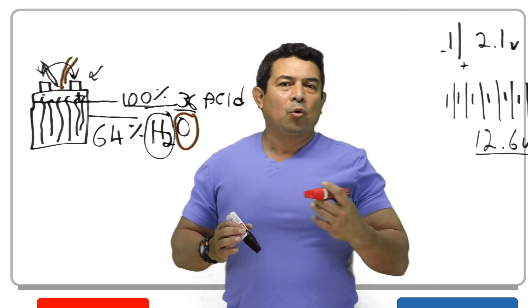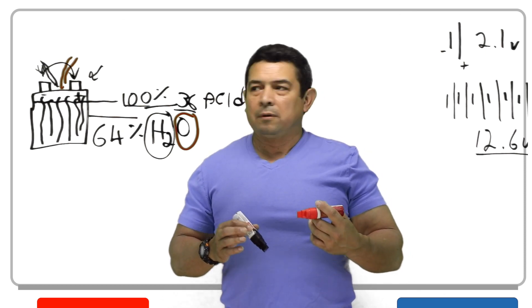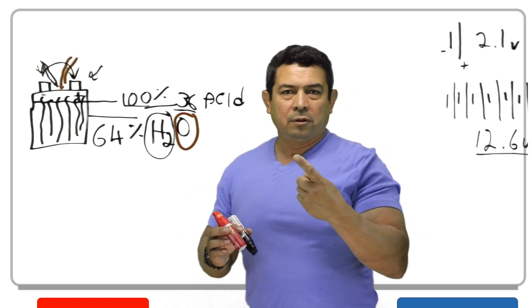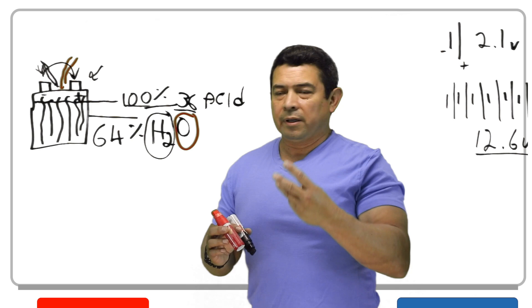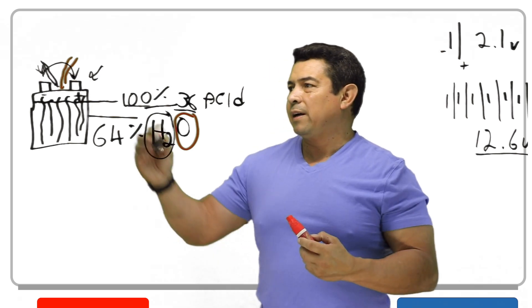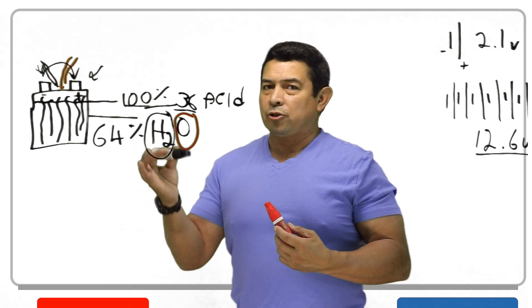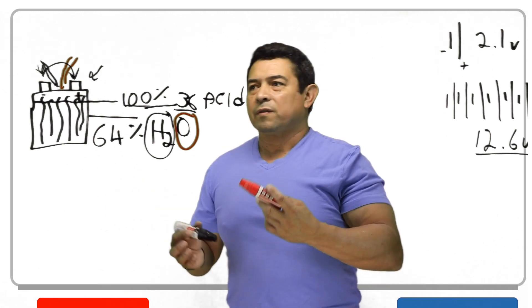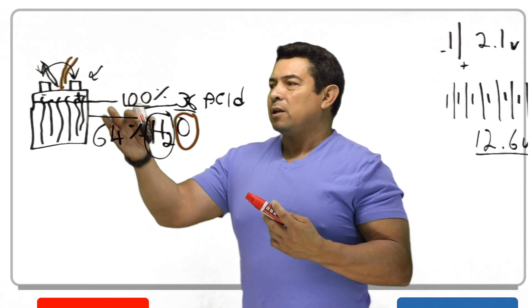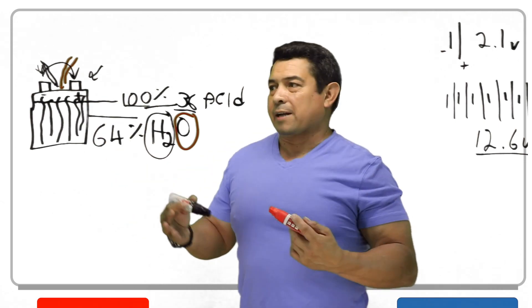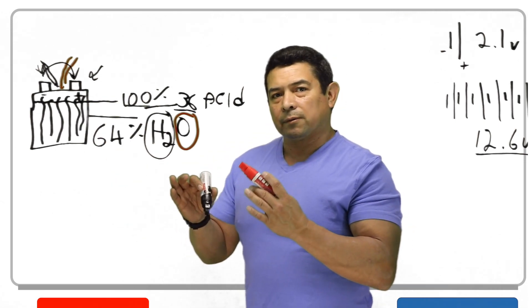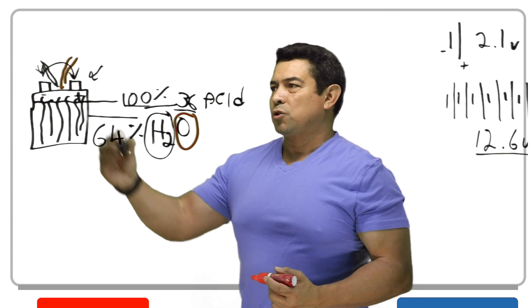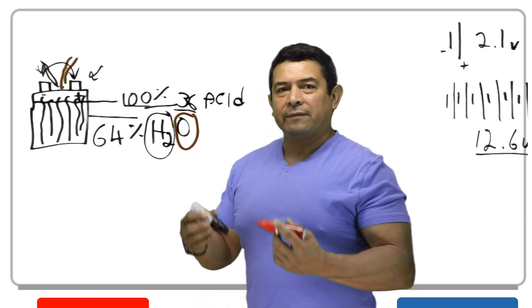Now let me ask you a question — what do you need for a fire? We need three things: fuel, oxygen, and heat. So now we have the hydrogen — that's the fuel — and we have the oxygen. And if someone comes in and creates a spark, or if someone comes in smoking, then you're going to have a fire. So we have to be very, very careful around batteries that are charging.